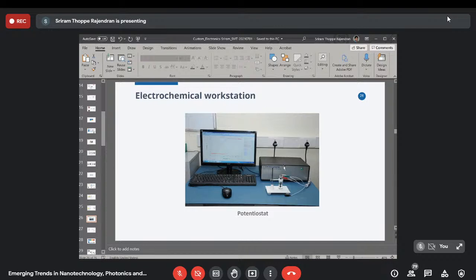And this machine is called a potentiostat because it can control potential, and it can also control current. It can either be a potentiostat or a galvanostat, meaning the galvanostat keeps the current constant and measures the change in potential, or the potentiostat keeps the potential constant and measures the current. And then depending on the requirement and the type of measurement, we can do more such modifications.